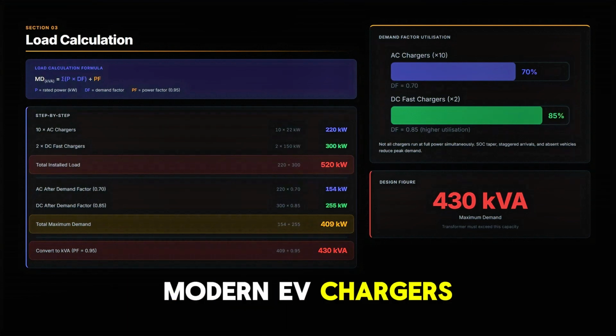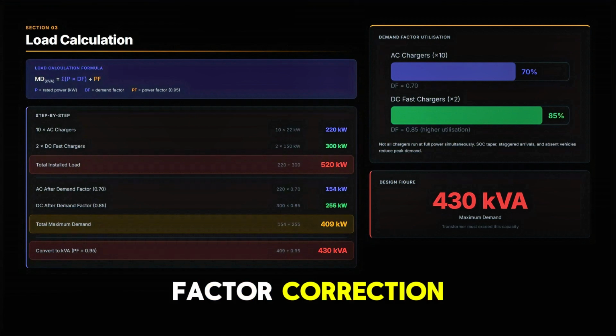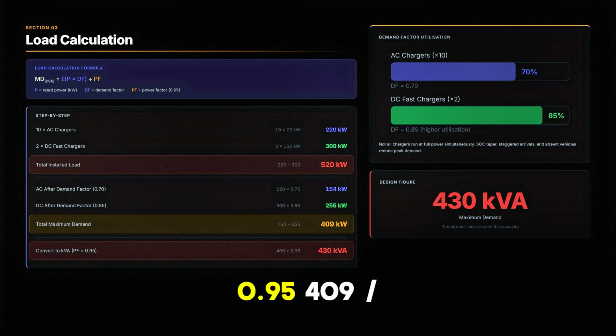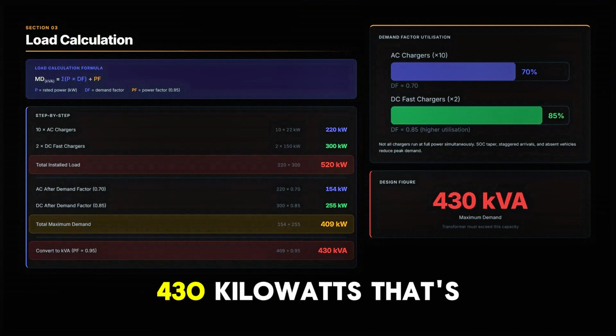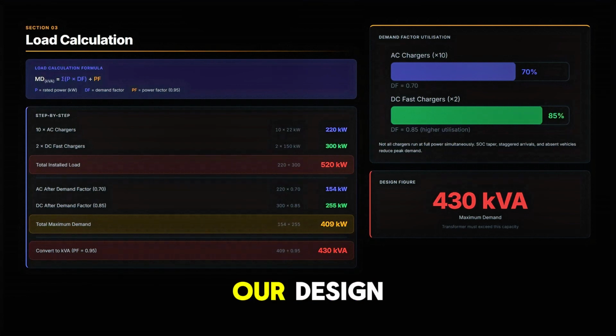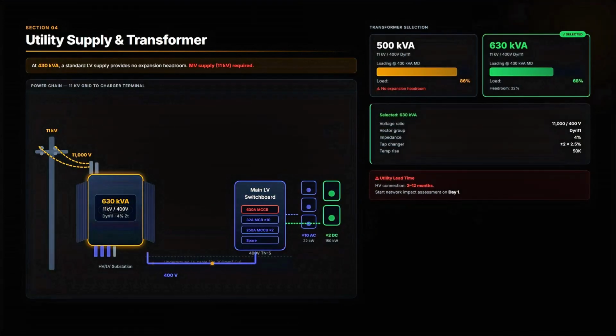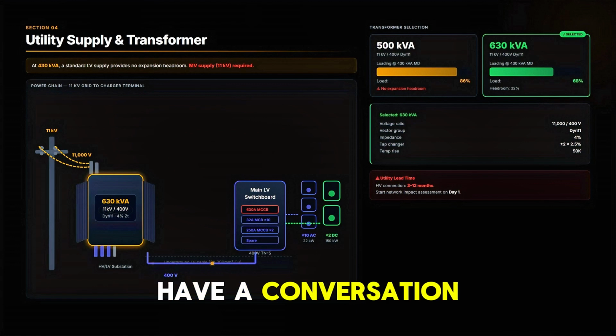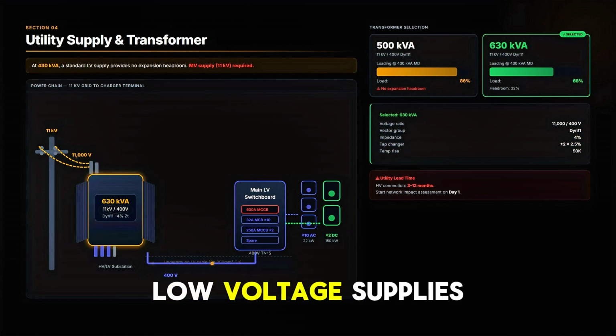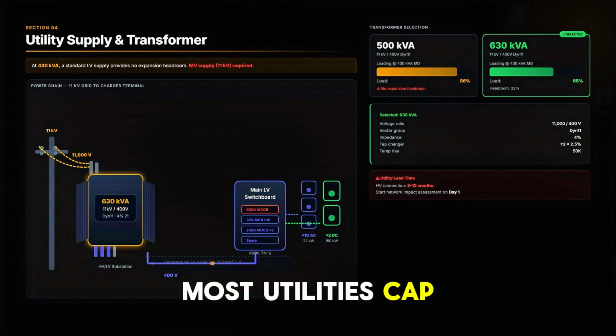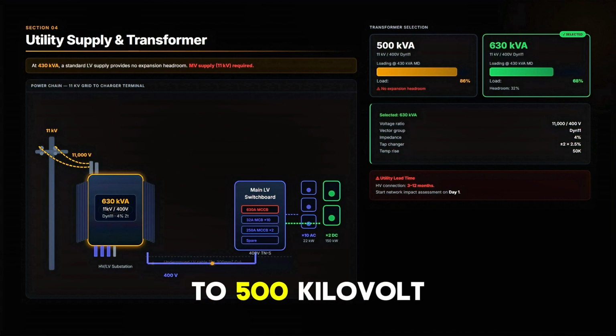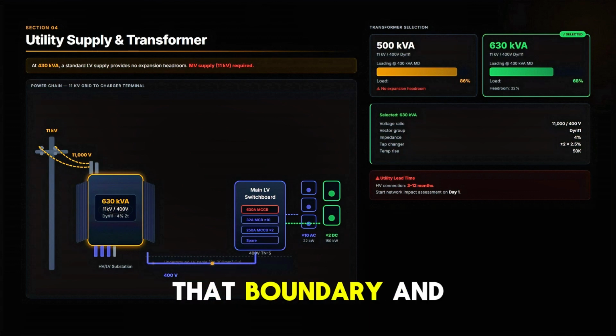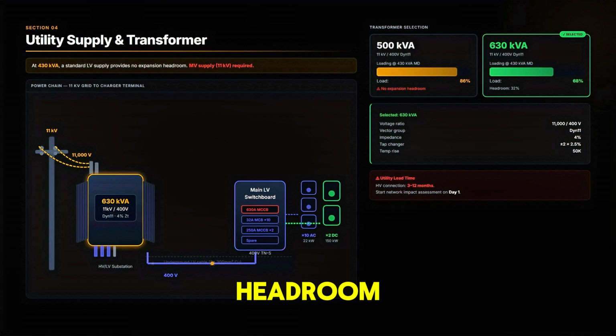Now convert to kilovolt amps. Modern EV chargers have active power factor correction. We'll use a power factor of 0.95. 409 divided by 0.95, 430 kilovolt amps. That's our design figure. 430 kVA. 430 kilovolt amps means we need to have a conversation with the utility. Low voltage supplies, most utilities cap these at 3 to 500 kilovolt amps. We're right at that boundary and we want expansion headroom. Medium voltage supplies the right call here.